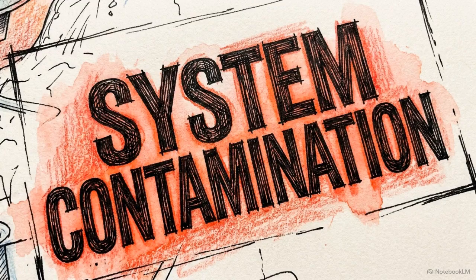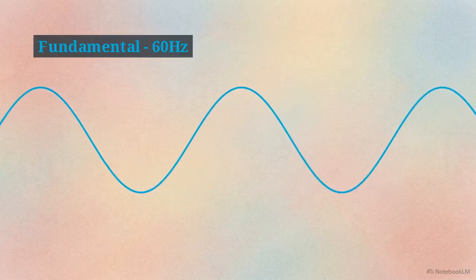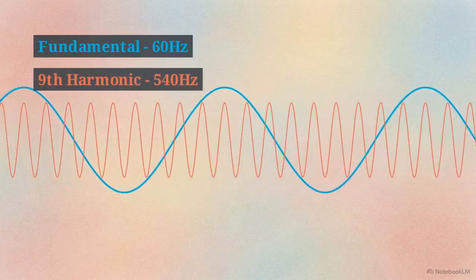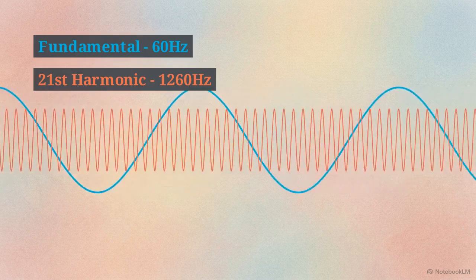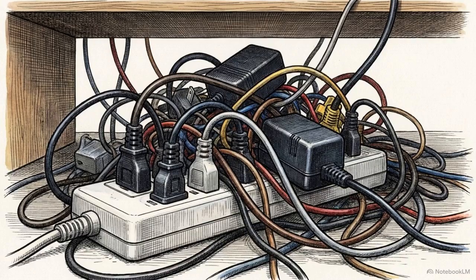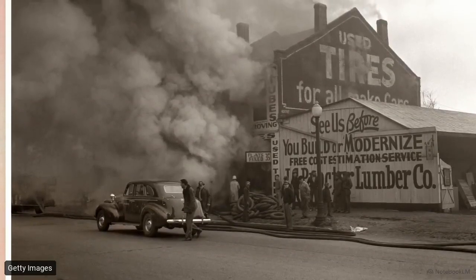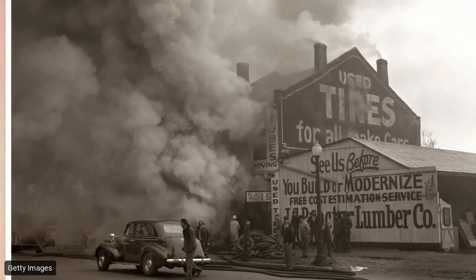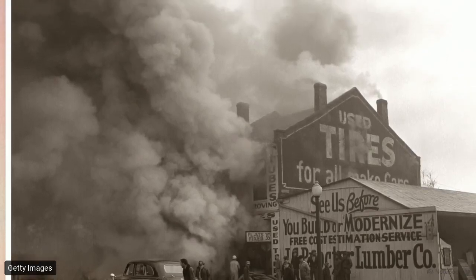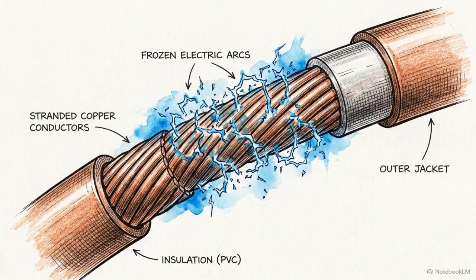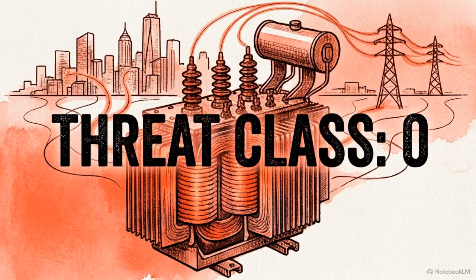That noise takes the form of specific rogue frequencies, known as Triplen Harmonics, specifically the 3rd, 9th, 15th, and 21st multiples of the standard power line frequency. Because early building codes didn't anticipate these frequencies, simply plugging in a floor full of standard office equipment can create a cumulative, invisible fire hazard deep inside the walls. Normal electrical noise often cancels itself out within the wiring, but triplens behave differently. Engineers classify them as zero-sequence currents, meaning they share a highly destructive behavioral trait.